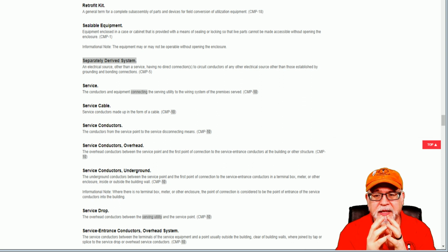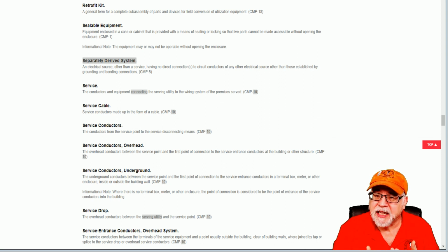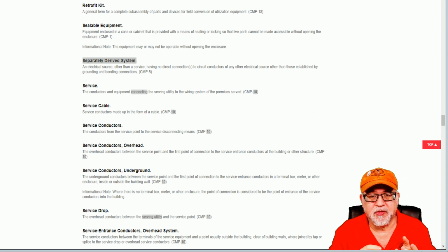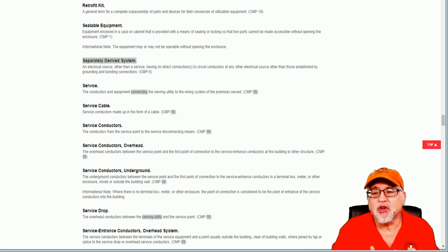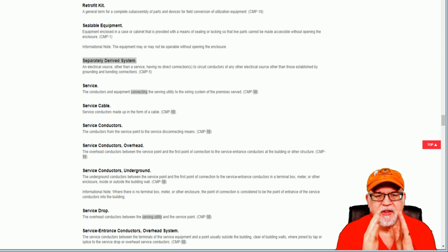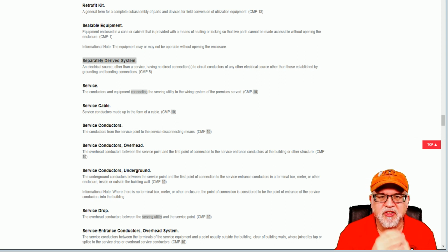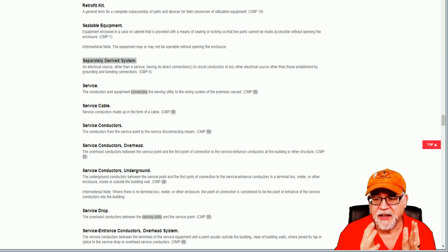They create magnetic coupling from primary to secondary, and when doing so, the grounding and bonding of the case and the equipment ground that's coming from the source, let's say an overcurrent device coming in from your service, hitting a transformer primary, you still have your grounding, you still have your bonding that you've got to do. So they are going to be intimate, but the primary to secondary are not. So it's literally two separate systems. And so that would be considered separately derived systems from primary to secondary.